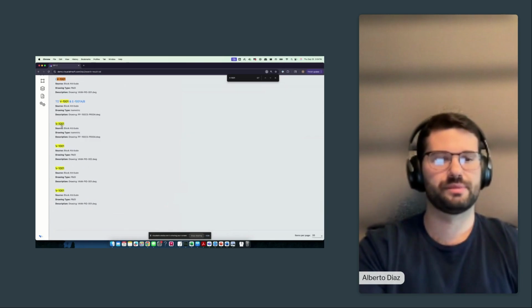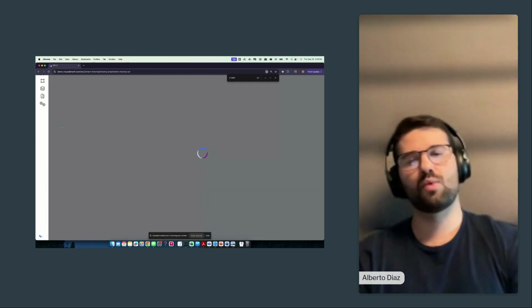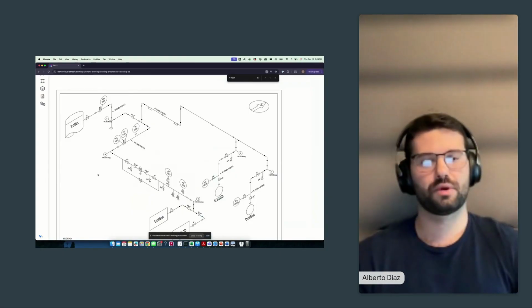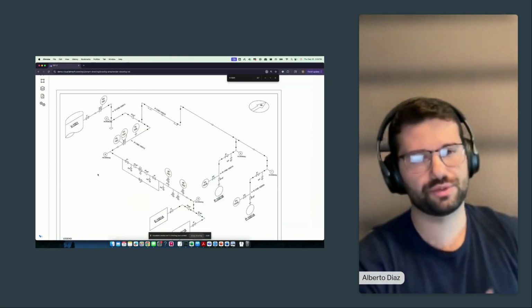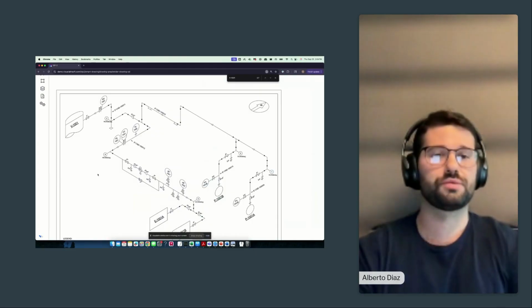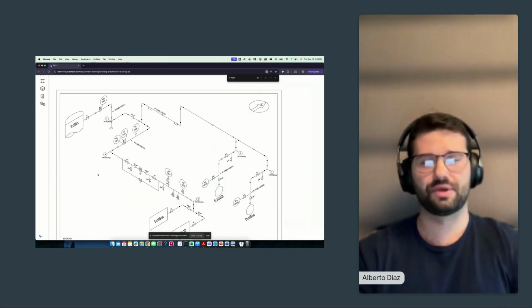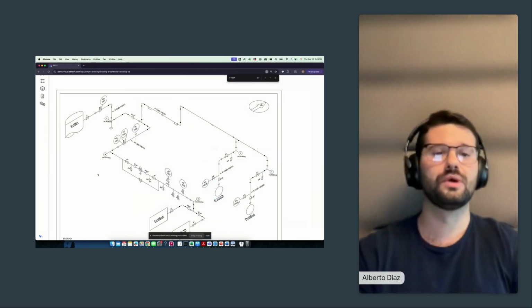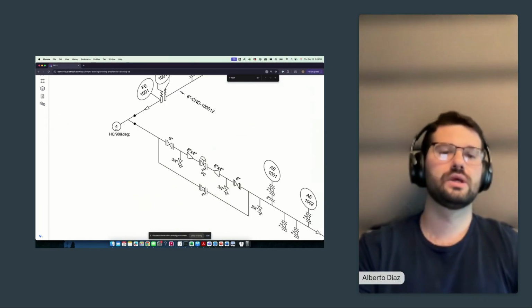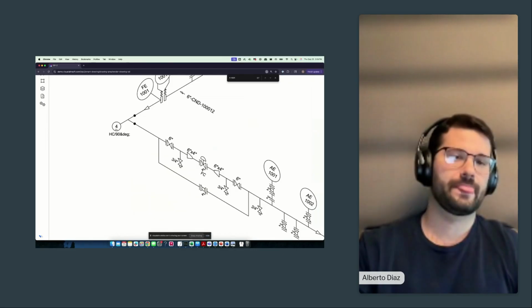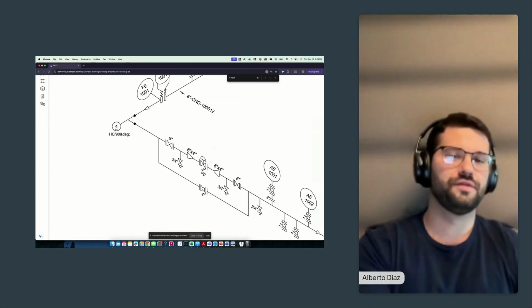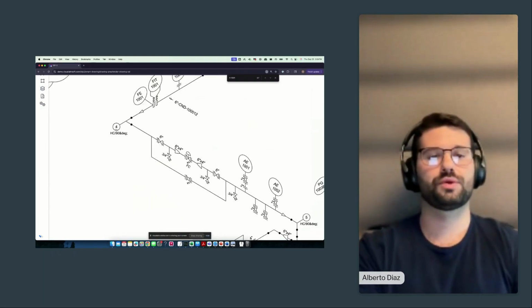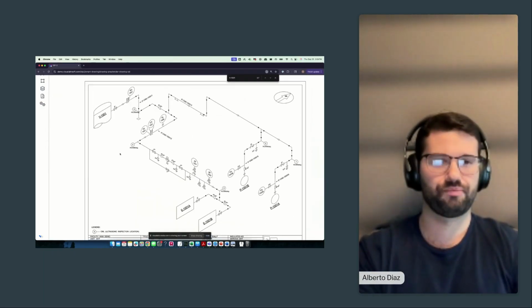So what this enables me to do, by clicking on that element, is quickly jump to that particular drawing and see if this is what I'm looking for. I purposely clicked on the isometric just to showcase the fact that those are also available, or you can enable the connection to them. And one of the key things that a lot of our customers like to do is tying the CML points back to the IDMS data so that you can click on a CML, view the corrosion history, view the different thickness dates, and essentially trend out what the corrosion is at any particular CML.